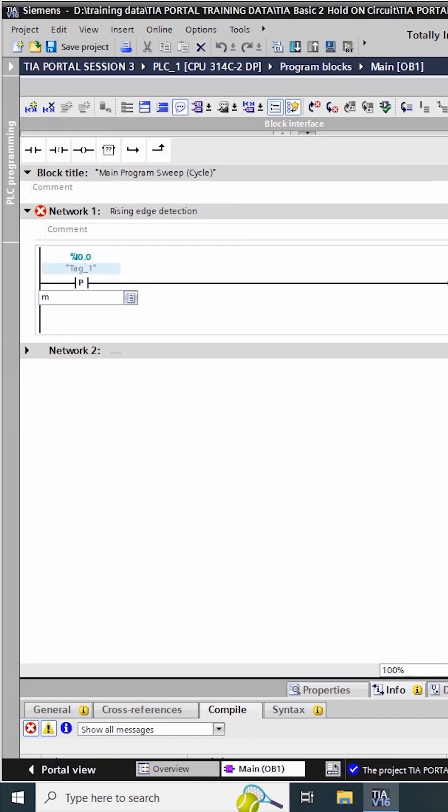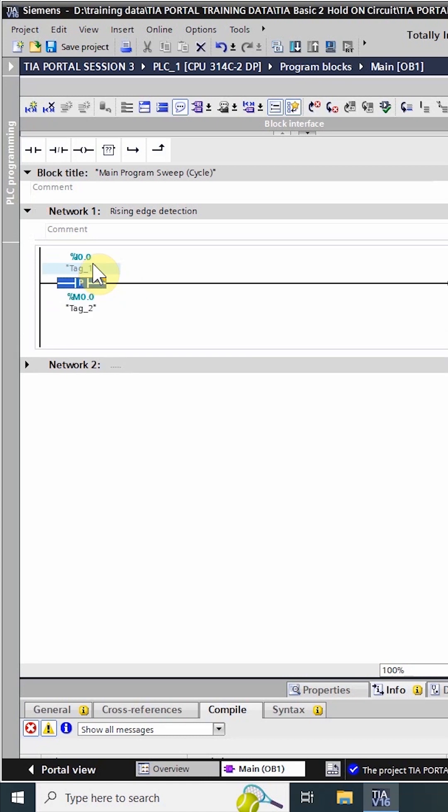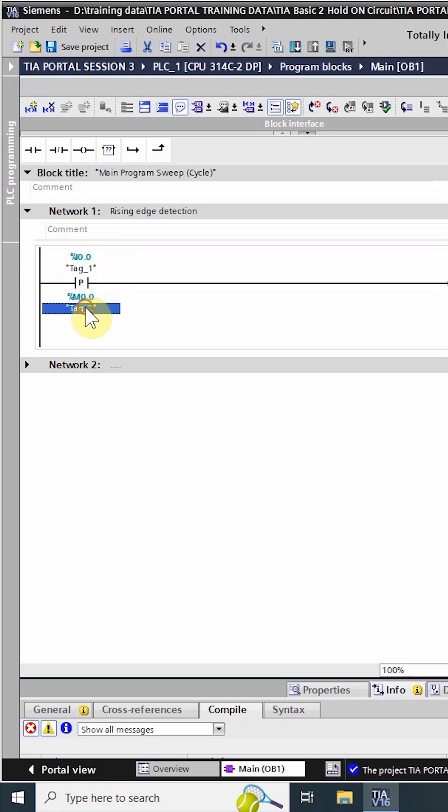Now this instruction will store the current state of the input i0.0 in the bit m0.0 and start comparing i0.0 input and bit m0.0. Whenever the input i0.0 goes high, this instruction detects a rising edge.